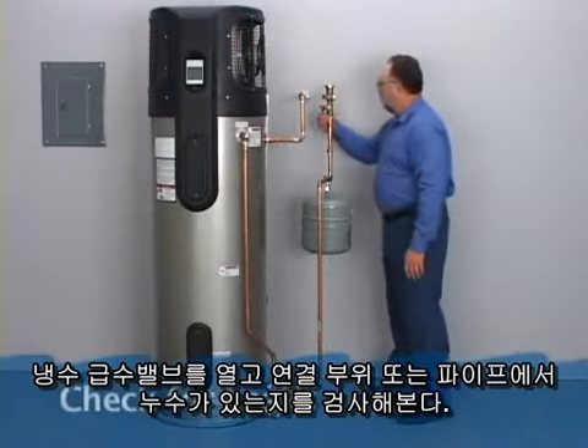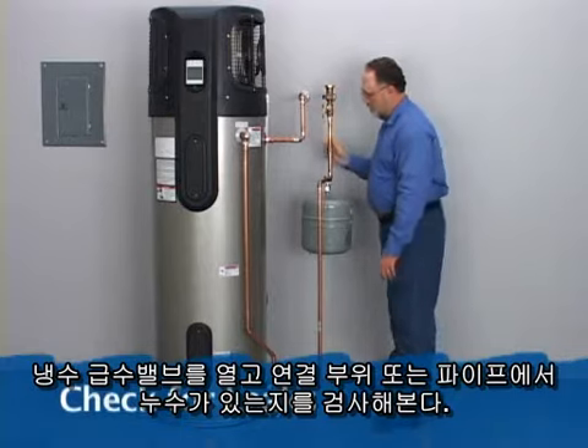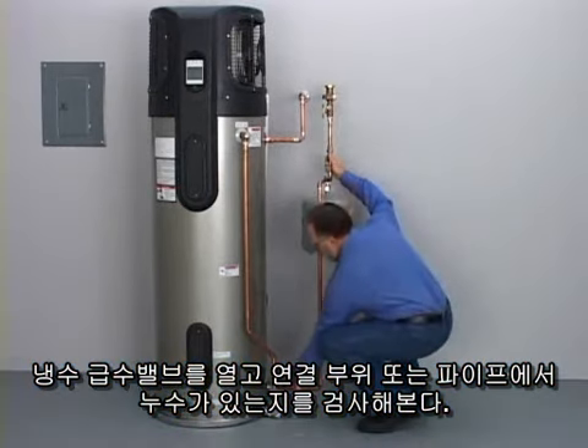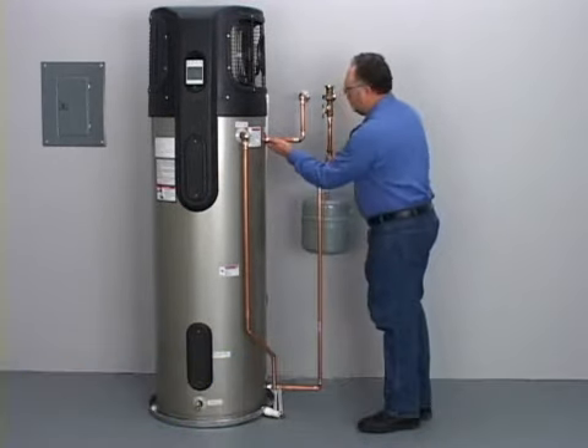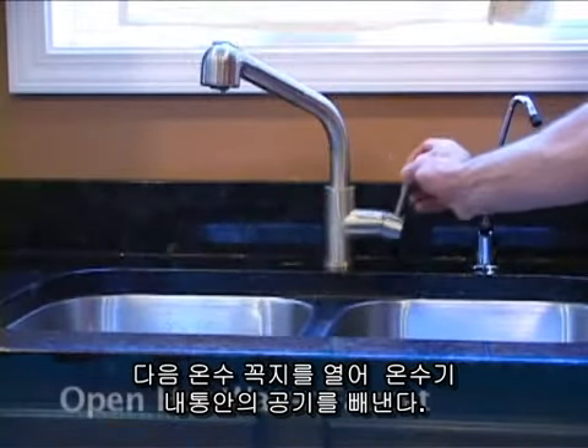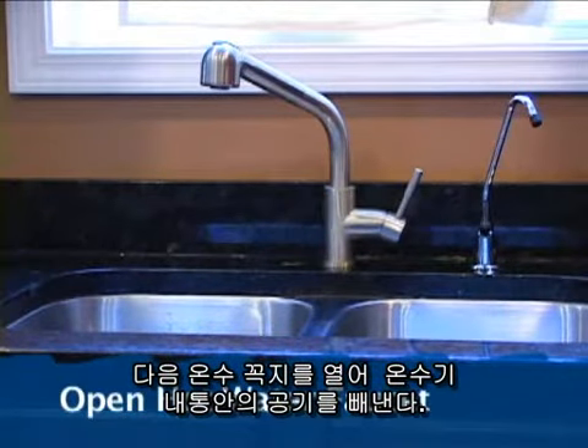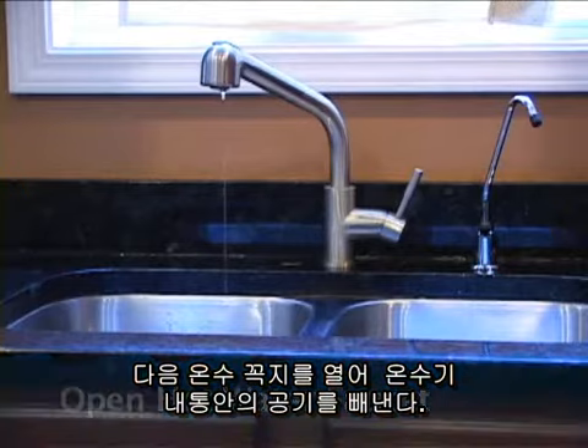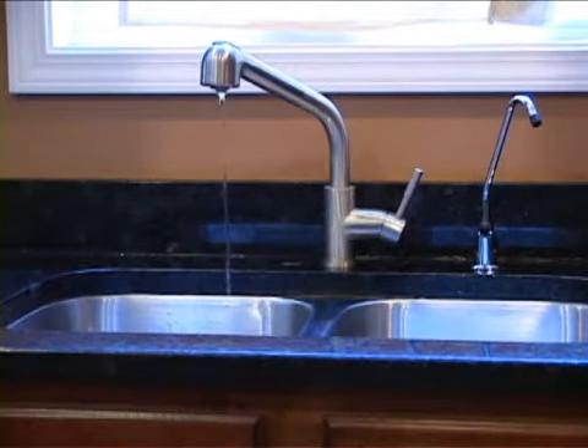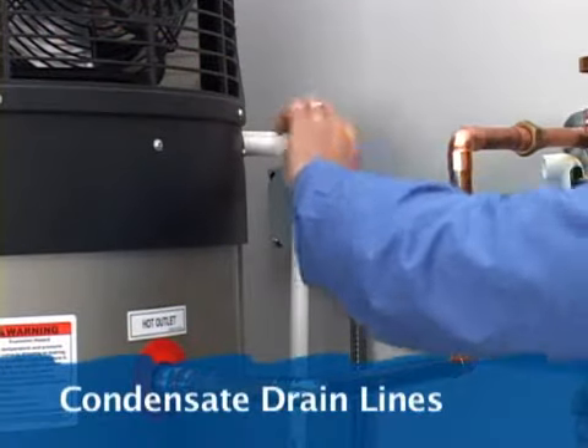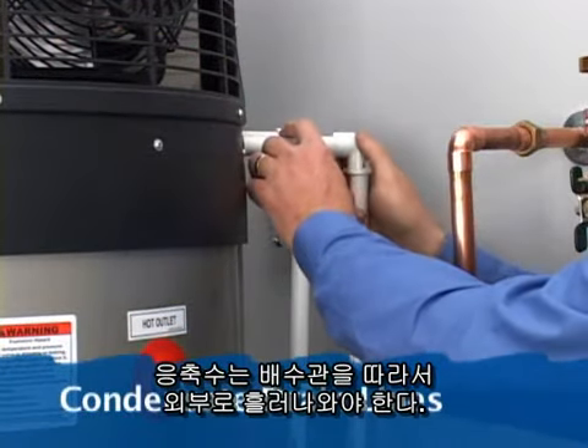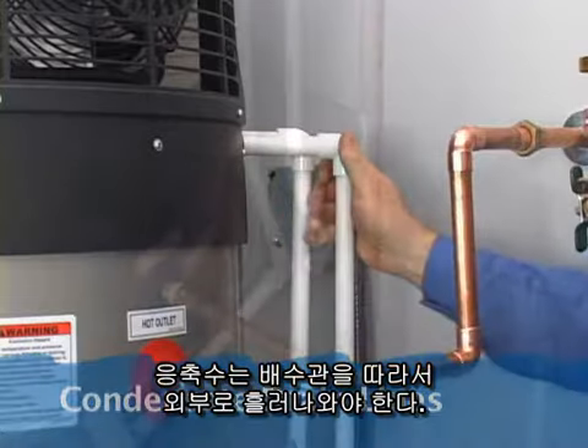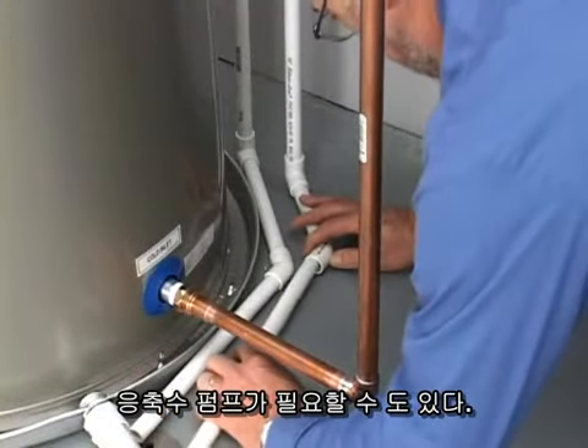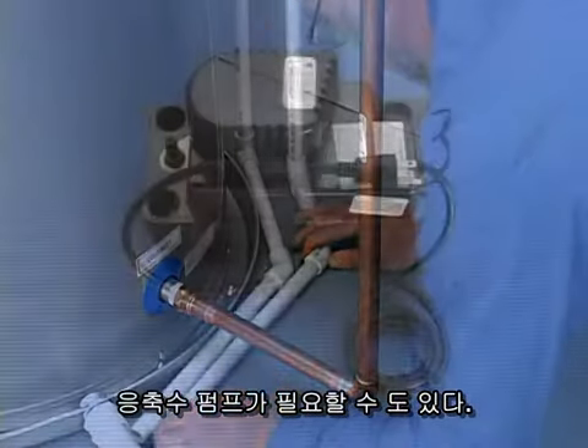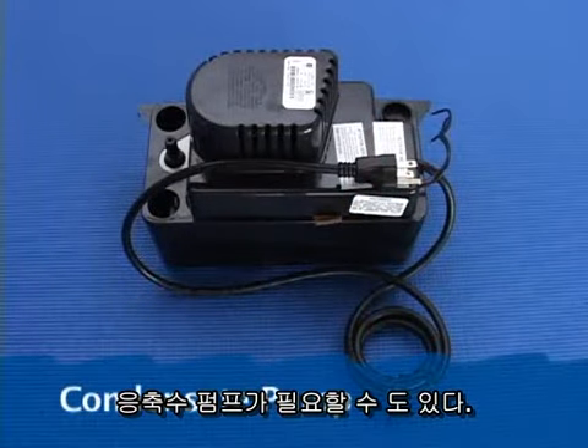Turn the cold water supply on and check for leaks. Almost all leaks are due to improper connections, not a tank leak. Open a hot water faucet until the water runs full to let air out of the tank. Next, attach the condensate drain lines. These two drain lines should slope to a floor drain or outside. In some installations, such as basements, you may need to install a condensate pump.